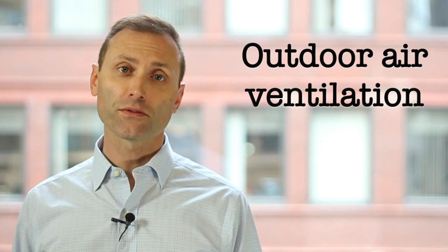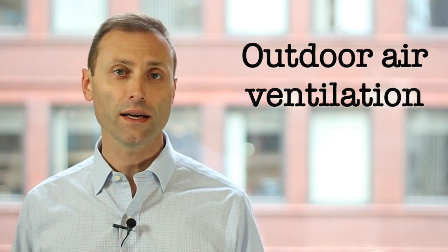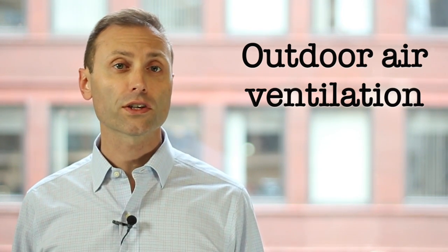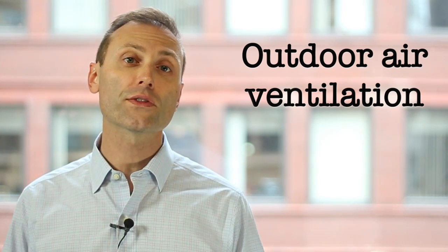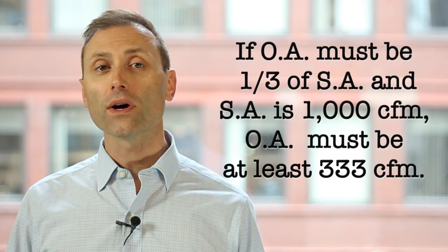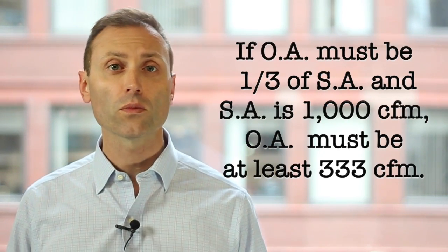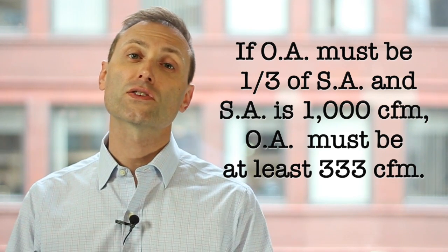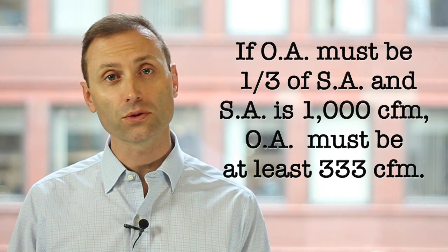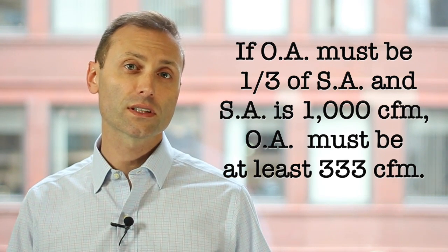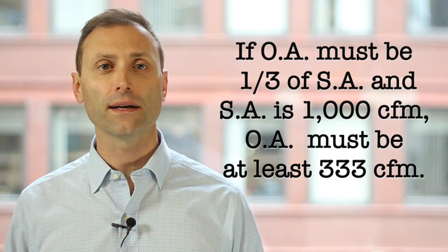Are there indoor air quality implications with VAV systems not found in other systems called constant volume systems? Certainly. Outdoor air ventilation is often provided as a percent of the total supply air. Here in Chicago, large commercial buildings are required to have at least one-third of the supply air come from the outdoors. So for the Chicago example, if 1,000 cubic feet per minute, or CFM, were supplied to a space, at least 333 would need to be from outdoor air ventilation, with the remaining 667 CFM being recirculated air.